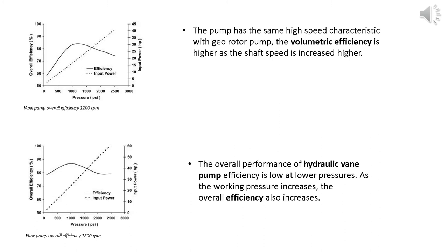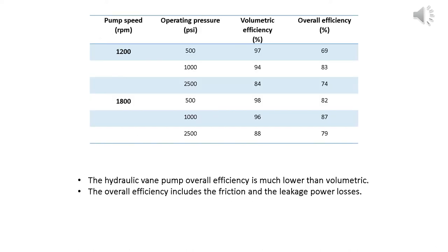There are two plotted graphs about the overall efficiency of vane pump at different speeds. The pump has same high-speed characteristic with georotor pump - the volumetric efficiency is higher as the shaft speed is increased. The overall performance of hydraulic vane pump efficiency is low at lower pressures. As the working pressure increases, the overall efficiency also increases. The hydraulic vane pump overall efficiency is much lower than the volumetric efficiency. The overall efficiency includes the friction and the leakage power losses.